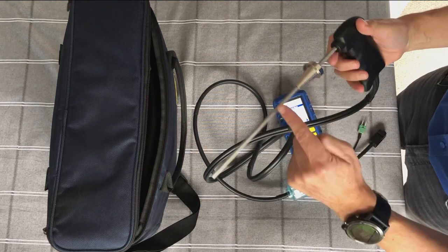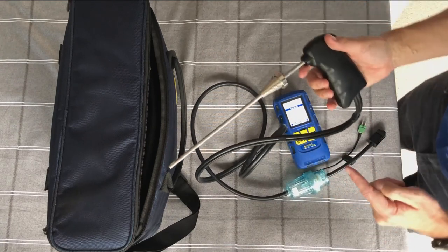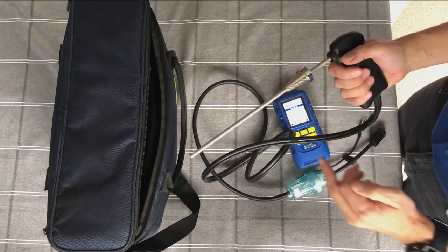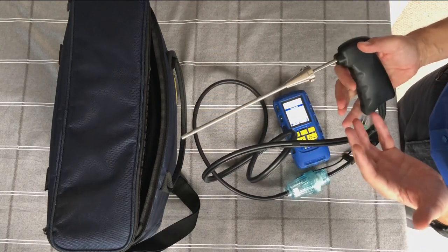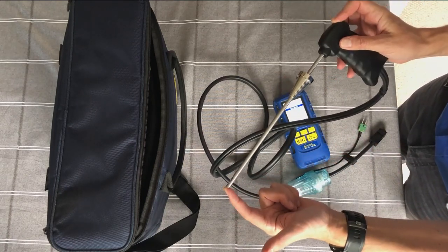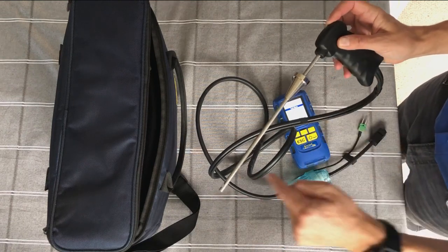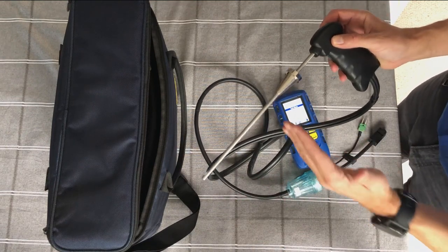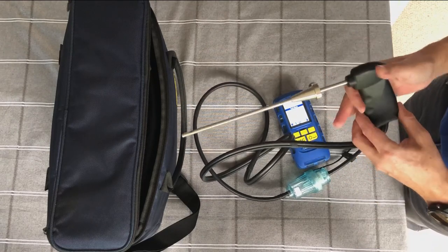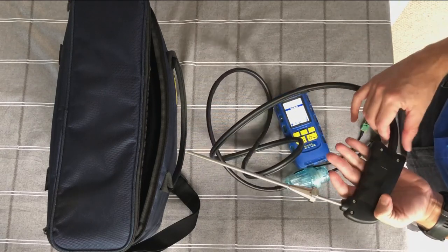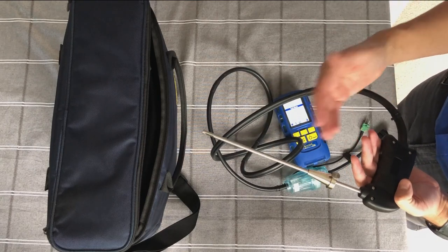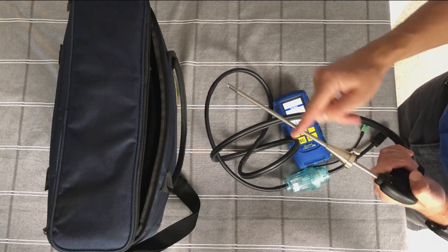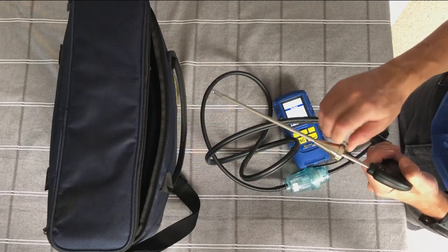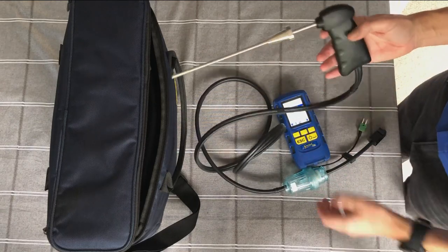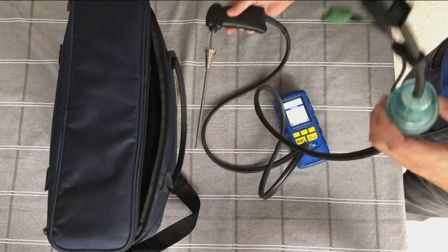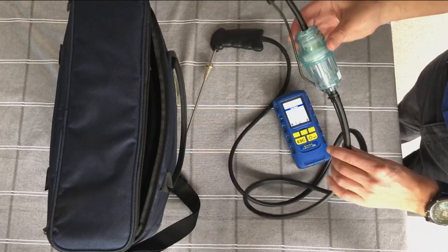Some of you will have kits with a bent probe. If you've got one of those, I think it's well worth having. That's for difficult access, because this has to be a certain length for the British standard. So we do a bent probe to allow you to get into tight spaces. If you've got a boiler mounted inside a kitchen cabinet, you've all experienced it. It's quite hard to get your flue probe in, if not impossible. So the bent probe, if you've got one, will allow you access. And that's that. So the other end, you've got your flue hose.